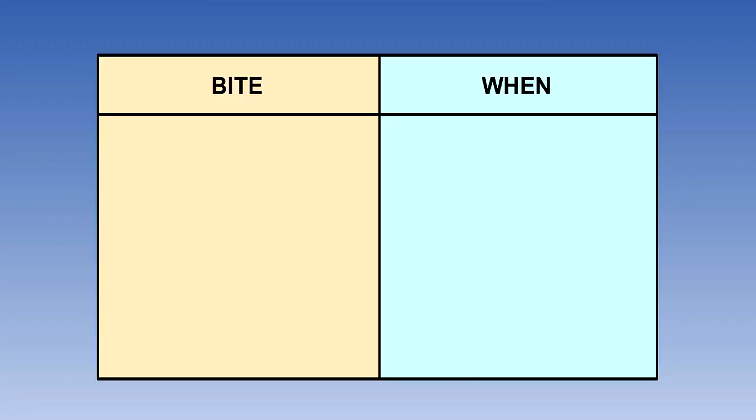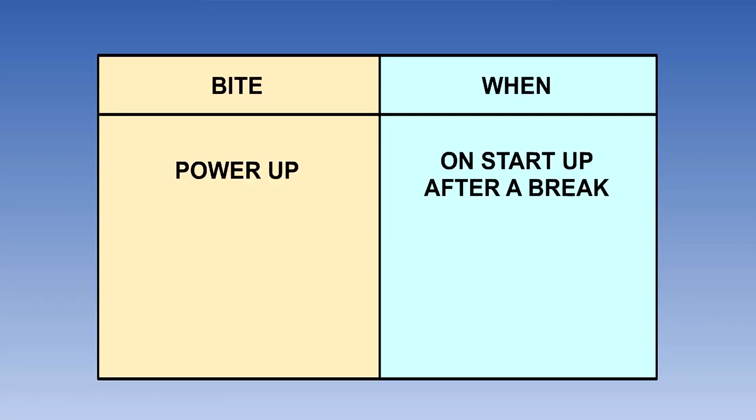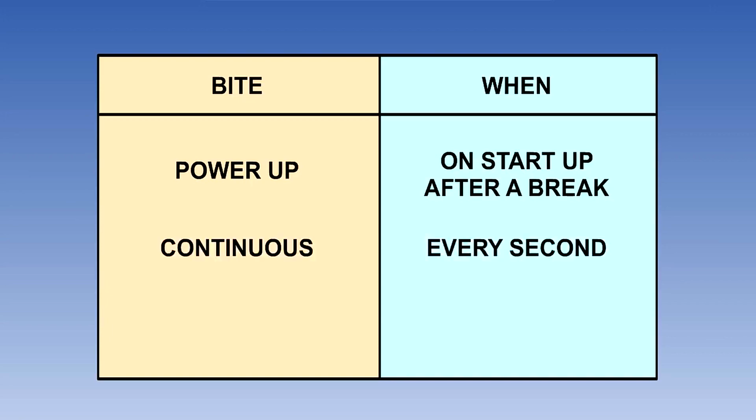A built-in test function which can be abbreviated to BIT is fitted to many types of modern computer-based instrumentation. It can also be known as built-in test equipment or BITE. There are three main operating modes. The first is at startup. This is called power-up. The second is continuous operation. A self-test routine will take place about once a second during the whole of the flight.